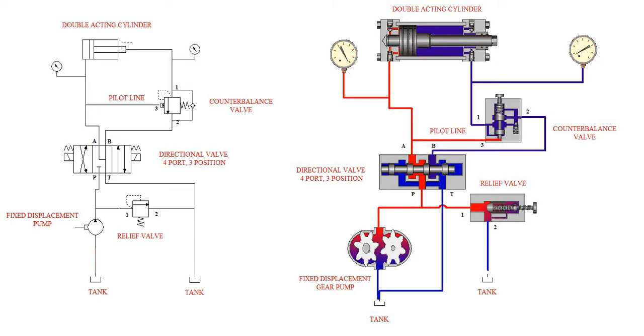So now I will advance it again, and you see at this point between those last two frames the relief valve closed off. So now the pressure here, it's easier. The fluid takes the path of least resistance, which in this case is into the piston end of the cylinder. So at this point, what do we want to look at? Well, for one, the red is indicative of the higher pressure. Blue is indicative of the lower pressure, and there are varying colors in between that represent the intermediate pressures.